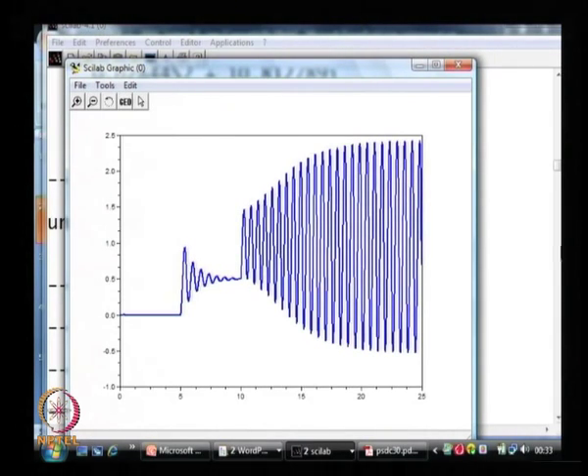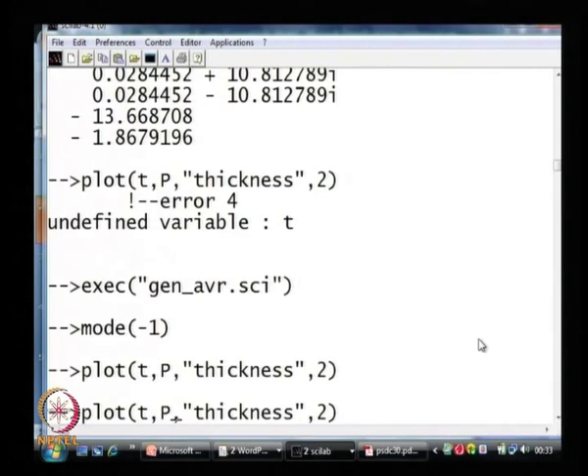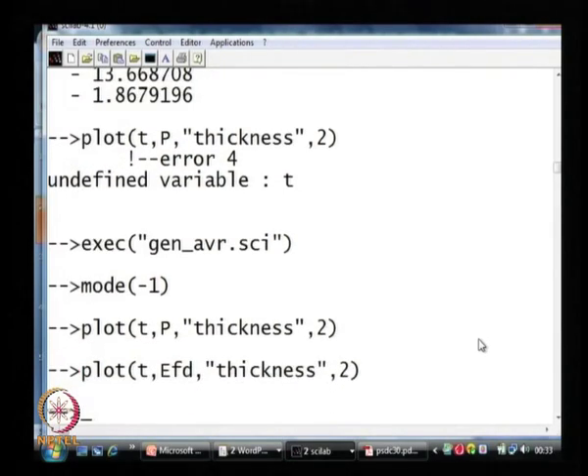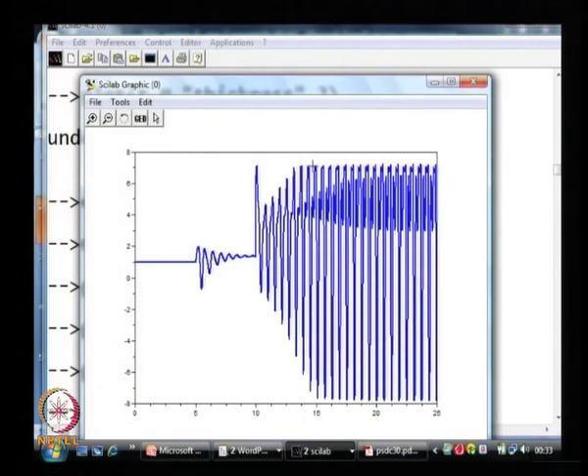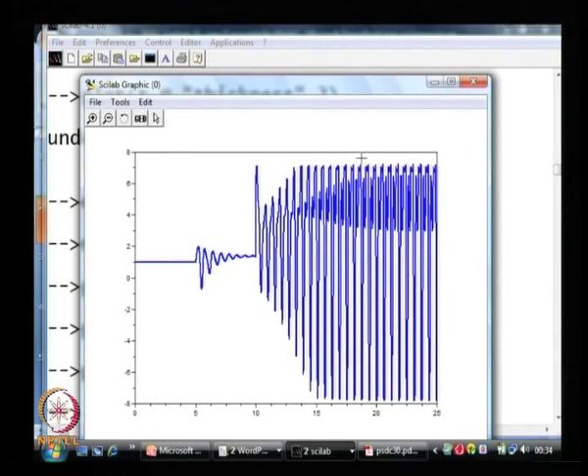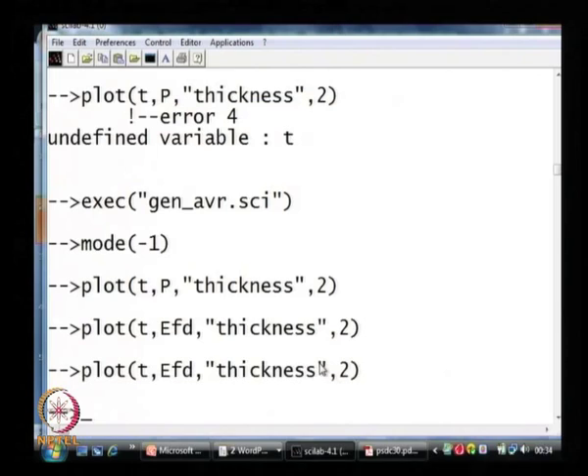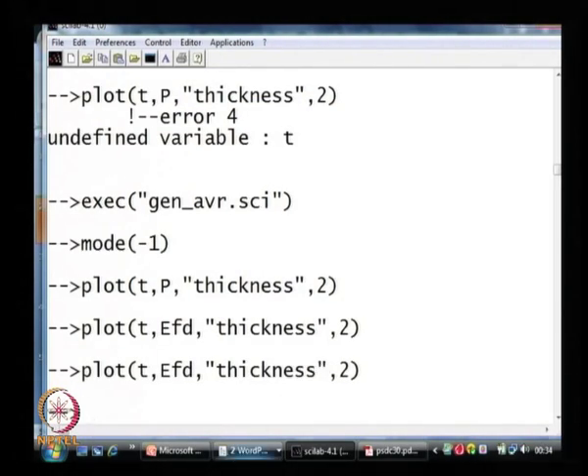The origin of this behavior is itself an interesting dynamical phenomenon. If you look at the field voltage, it seems to also oscillate and is clipped to a certain value. It is clipped because the static excitation system has limits—that is the reason why it is getting clipped.